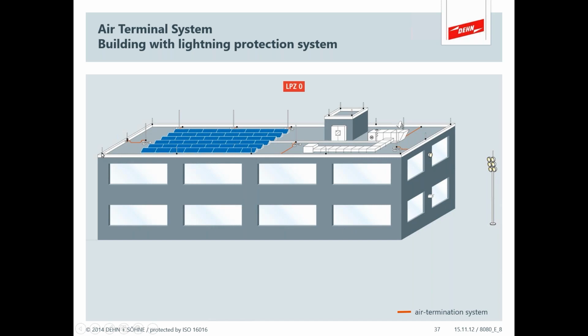For instance, here at the edge of the building, it's reasonable to use the parapet side, the metal flashing maybe of a building is very common. And then that has to be bonded. So here you have an air terminal, lightning down conductor connections, and equipotential bonding. But notice over here, you have what can be an air terminal mast in the center of the structure, and it's preventing attachment onto these victim structures like the air chillers, the handlers, your solar arrays, your photovoltaic array. And it's separating the lightning from that structure and still acting as an air terminal.